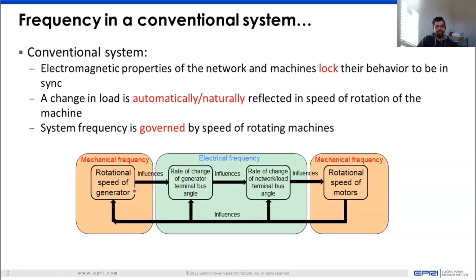If you have a change on the load end, that is naturally reflected in the speed of rotation of a machine, and you can govern everything, especially the electrical frequency, by controlling the speed of your rotating machines. Since all of this is linked, consider what happens when you have an event on the system, especially a load generation imbalance event. Your frequency starts falling, and you need fast energy injection in order to arrest this decline. Then, to stabilize the frequency, you need some amount of controlled energy injection during the recovery period.